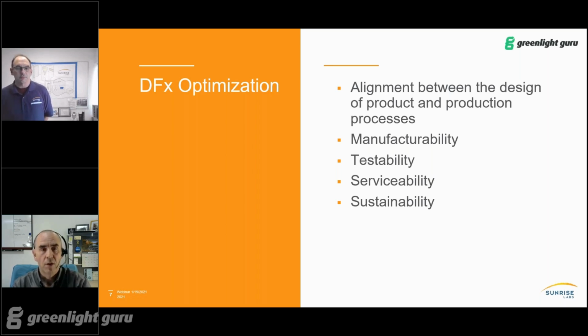There's also value in that being done in the same facility, so that if you're identifying a problem at the top level of the product, it may be easier to relate that to issues observed at the lower level assemblies. For example, you're testing a full medical device system at the facility, and you encounter a particular type of failure, and the test team involved with that product is very familiar with that type of issue — they know not only which PCA has that problem, but what component to go look at on that particular assembly.